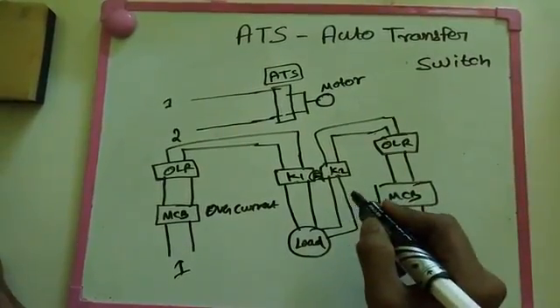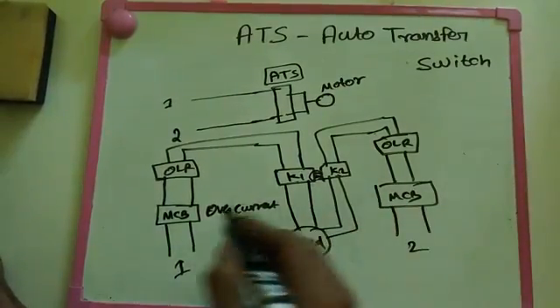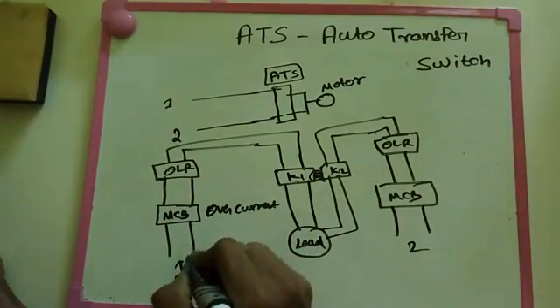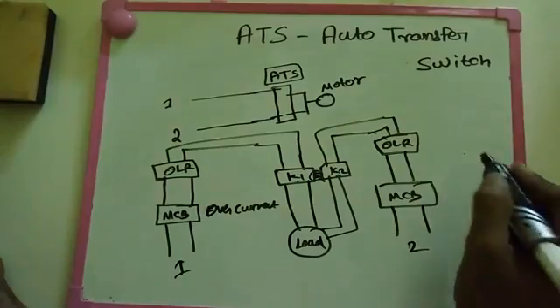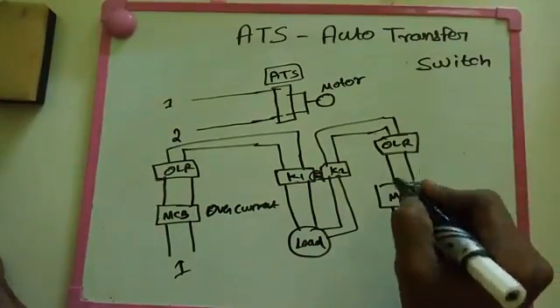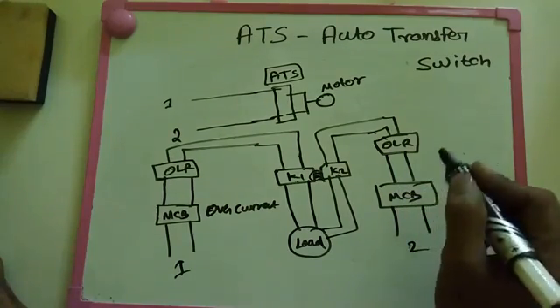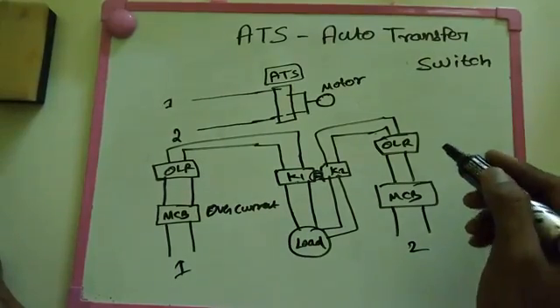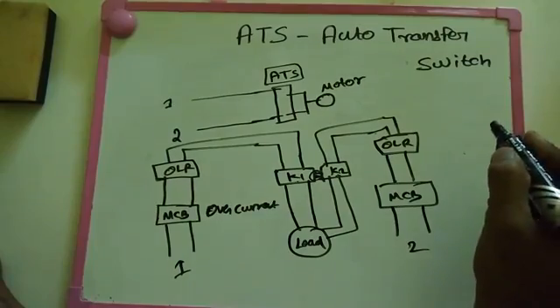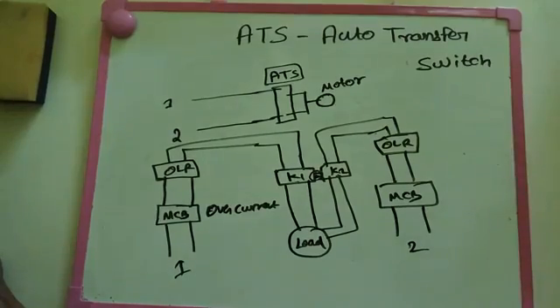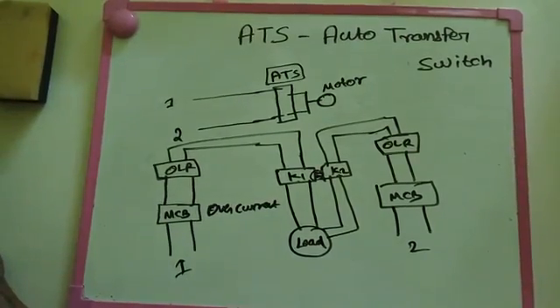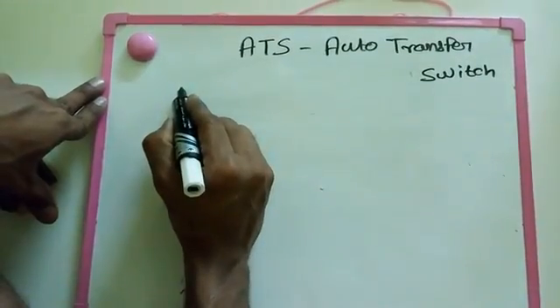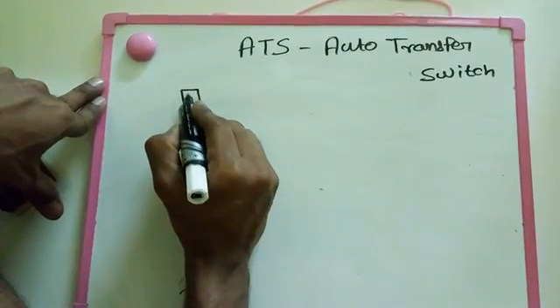Before showing the control diagram, we need to make a common power supply. We have two power supplies. If we make a control diagram and take the power supply from supply one, then if supply one is switched off, the total control goes to shutdown. If we take supply two, then if supply two is switched off, the total control goes to shutdown. So we need to make a common power supply - we make some relays and use them to make a common power supply.